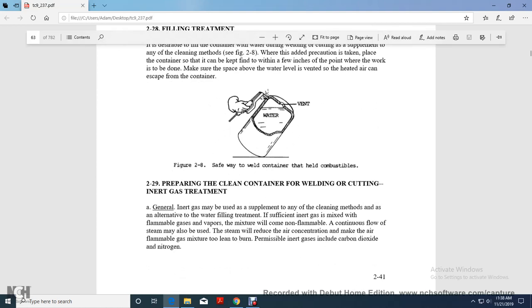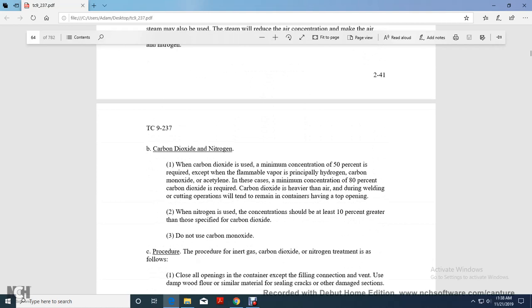Inert gas treatment. Inert gas treatment may be used to supplement any of the cleaning methods, or as an alternative to water filling, with treatment of sufficient inert gas to mix the flammable gas vapors into a non-flammable mixture. A continuous flow of steam may also be used. Steam will reduce the air concentration, because it makes the air and flammable gas mixture too lean to burn. Permissible inert gases include carbon dioxide and nitrogen. When carbon dioxide is used, a minimum concentration of 50% is required, except for flammable vapors of principally hydrogen, carbon monoxide, or acetylene. In these cases, a minimum concentration of 80% carbon dioxide is required.